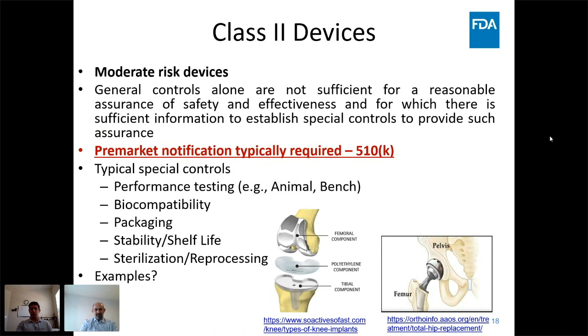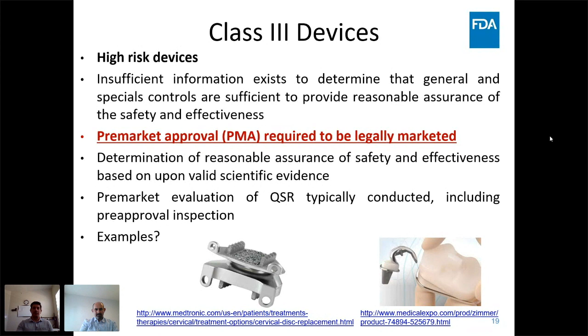Class 3 devices are high-risk devices. Basically, general and special controls are not sufficient for reviewing these devices or to demonstrate substantial equivalence. These devices are called pre-market approval, Class 3, as I said, the most stringent, time-consuming and expensive sort of review. Determination of reasonable assurance of safety and effectiveness is based on valid scientific evidence. Pre-market evaluation of quality system regulation is typically conducted, including pre-approval inspection. These devices are usually high risk, such as cervical disc replacement, heart valves, implantable neuromuscular stimulators, etc.